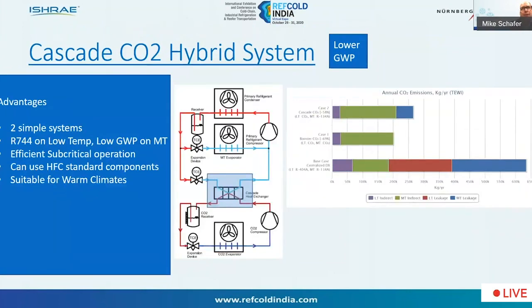So the advantages would be that there's two simple refrigeration systems that are easily understood and widely known. CO2 is used on the low temp and a low GWP refrigerant on the medium temp. The system operates very efficiently for the CO2 side because it's operating subcritically. The other advantage is that standard HFC components can be used. Very suitable for warmer climates. And then, of course, we already talked a bit about the CO2 emissions in the TEWI calculation. So the system looks very good from that perspective.